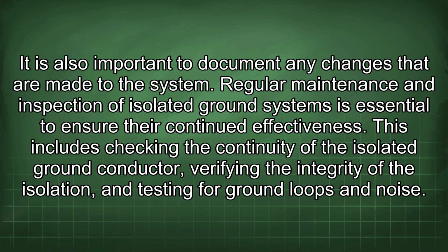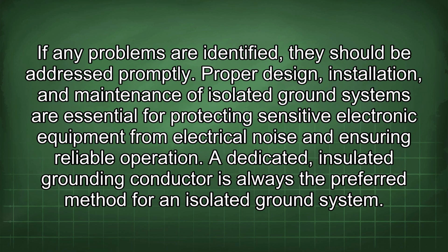Regular maintenance and inspection of isolated ground systems is essential to ensure their continued effectiveness. This includes checking the continuity of the isolated ground conductor, verifying the integrity of the isolation, and testing for ground loops and noise. If any problems are identified, they should be addressed promptly.